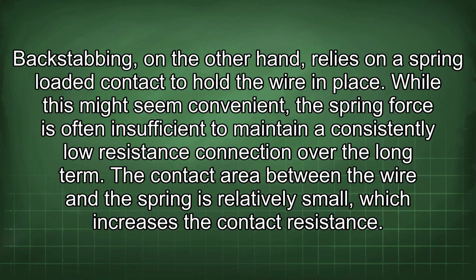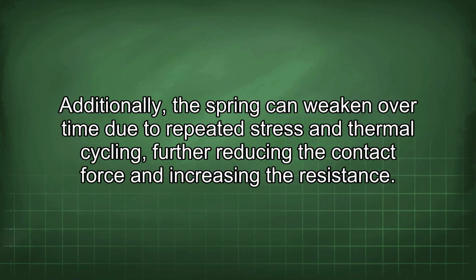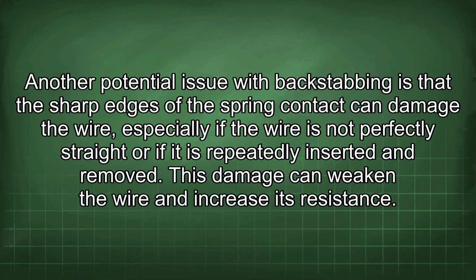While this might seem convenient, the spring force is often insufficient to maintain a consistently low resistance connection over the long term. The contact area between the wire and the spring is relatively small, which increases the contact resistance. Additionally, the spring can weaken over time due to repeated stress and thermal cycling, further reducing the contact force and increasing the resistance. Another potential issue with backstabbing is that the sharp edges of the spring contact can damage the wire, especially if the wire is not perfectly straight or if it is repeatedly inserted and removed. This damage can weaken the wire and increase its resistance.